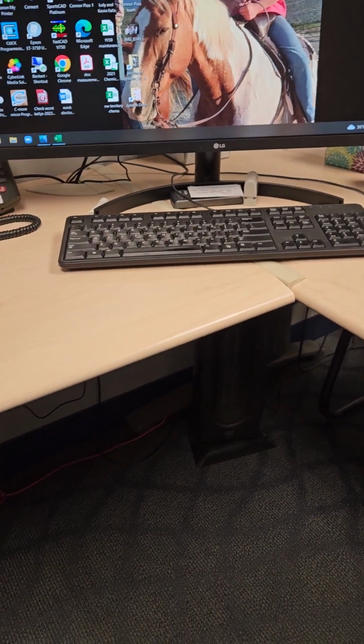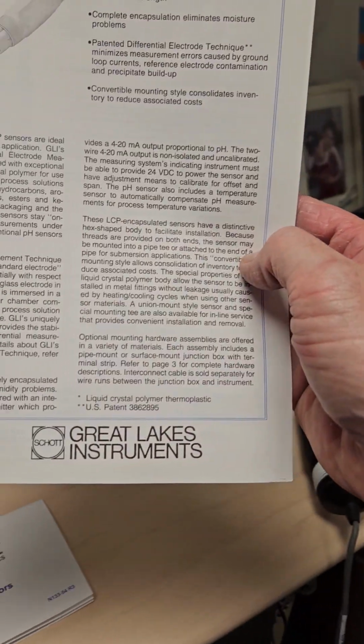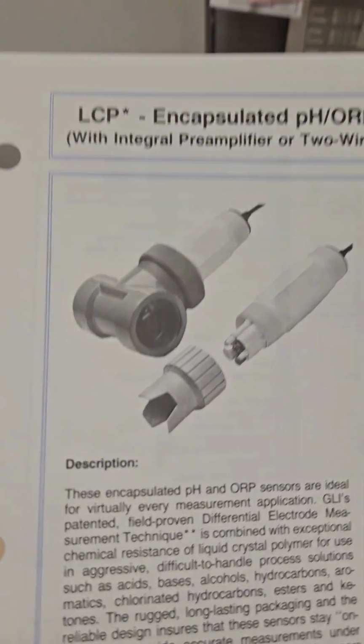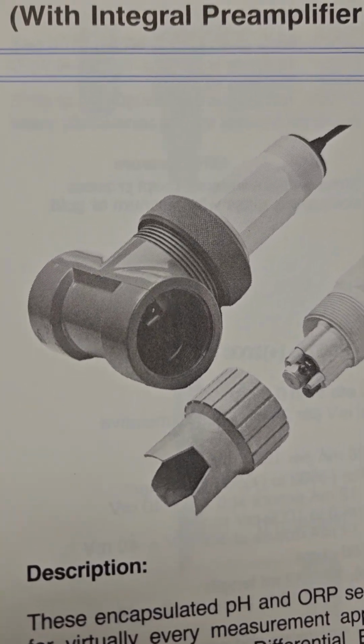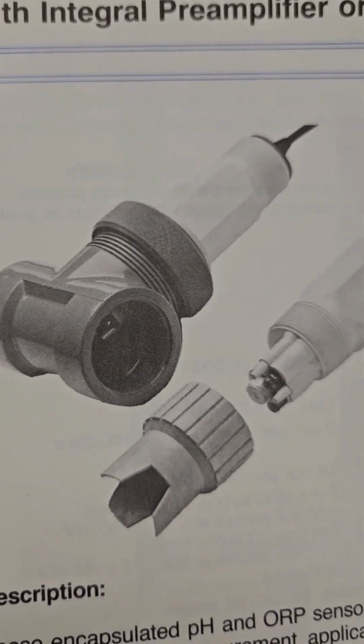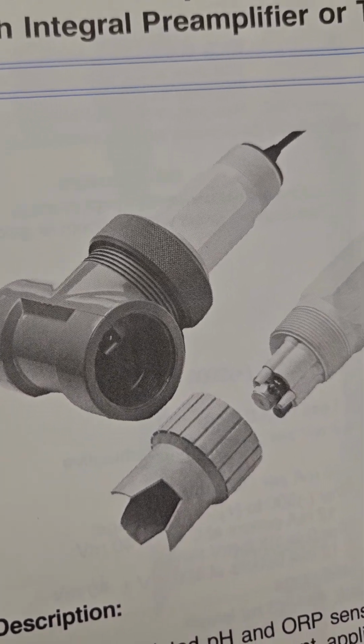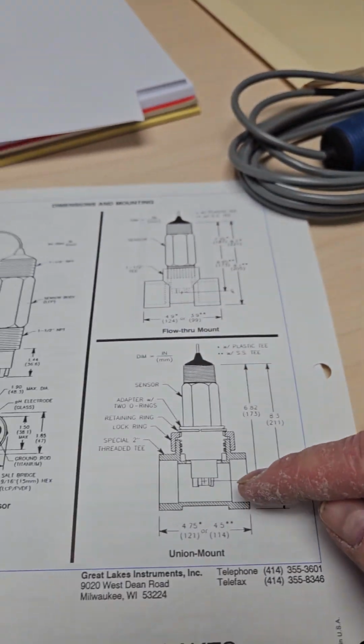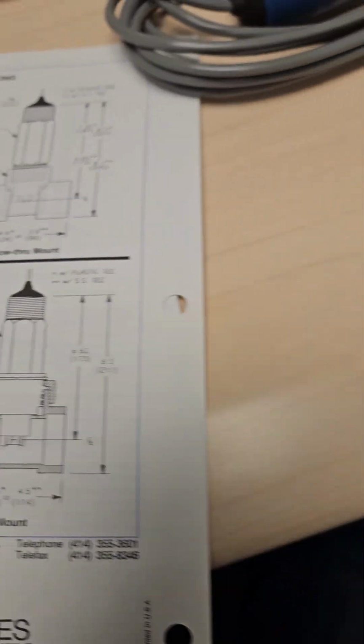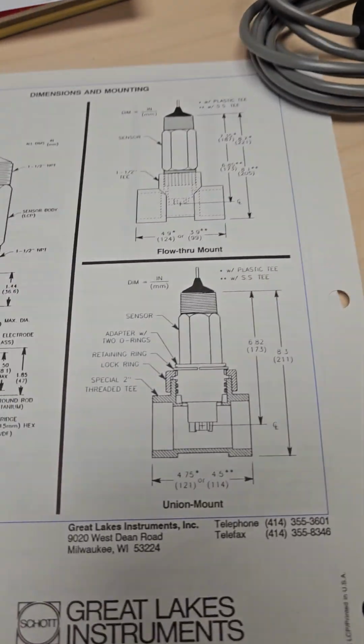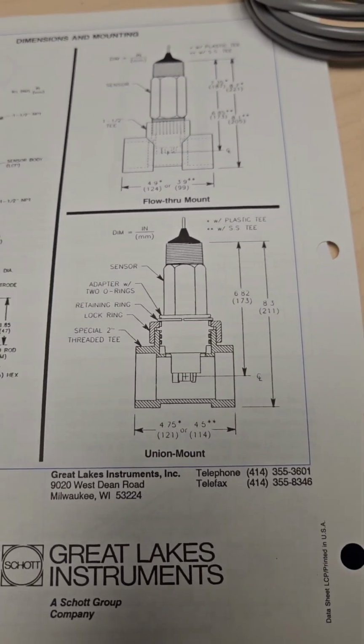We've since had to start using what they call convertible type probes, which have been around for a long time. This is a 30-year-old document from Great Lakes, printed in 1992. There's a union trap right there. So they offered the union trap; we just built our own with a Spears union. The union trap device is able to get this style larger body probe, the 1.5 inch convertible type probe, which is still made by most companies, down into the stream of water.